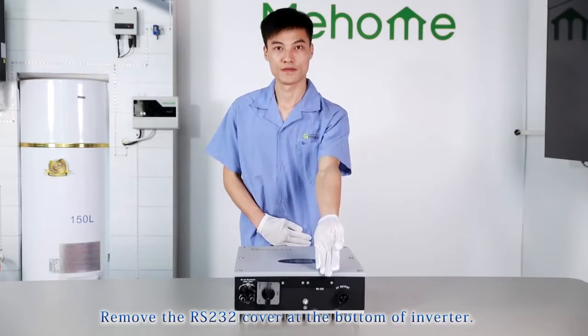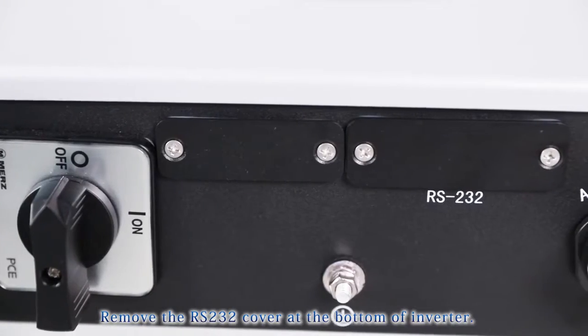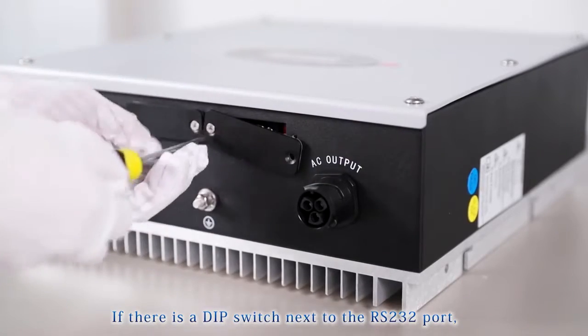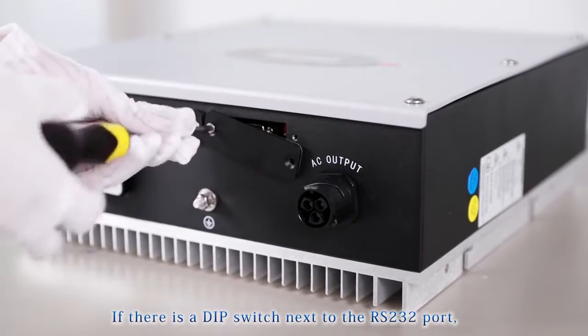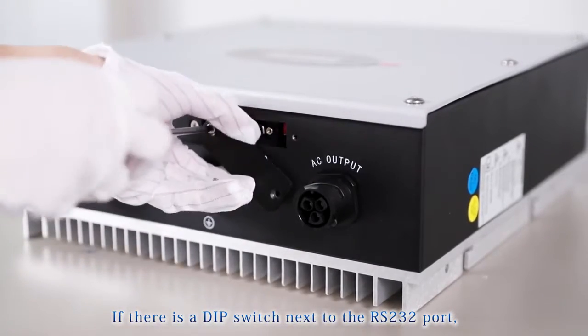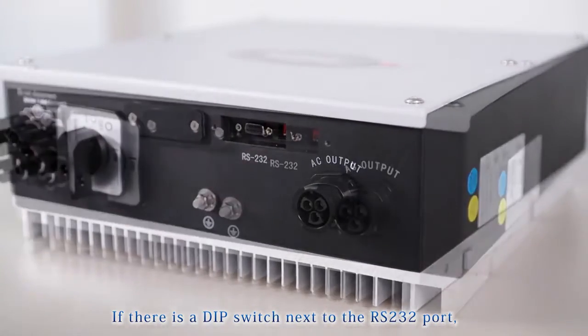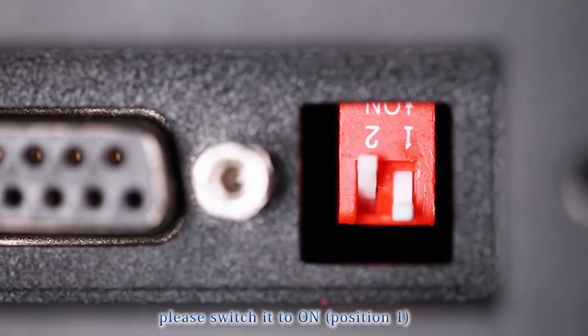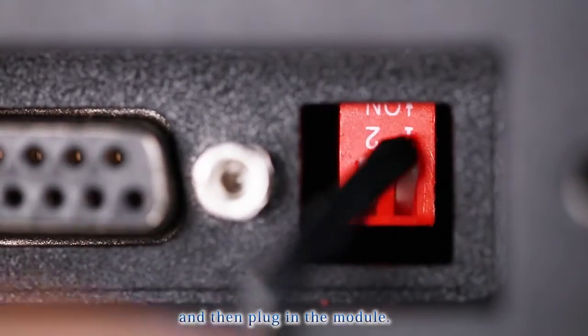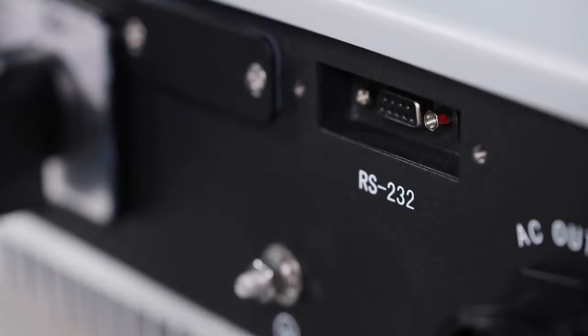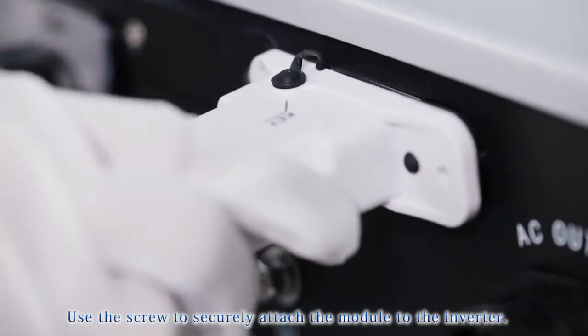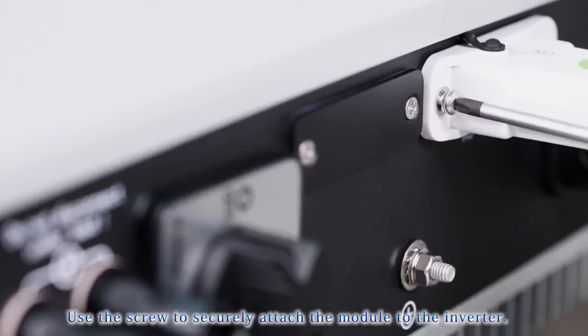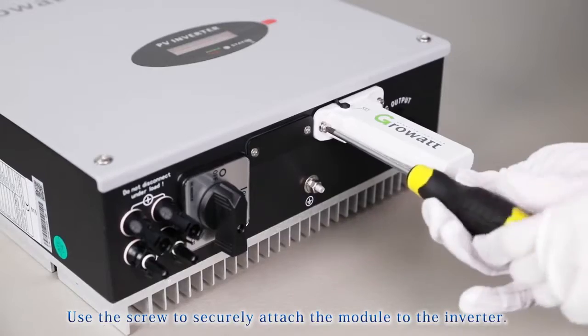Remove the RS232 cover at the bottom of the inverter. If there is a DIP switch next to the RS232 port, please switch it to ON position 1 and then plug in the module. Use the screw to securely attach the module to the inverter.